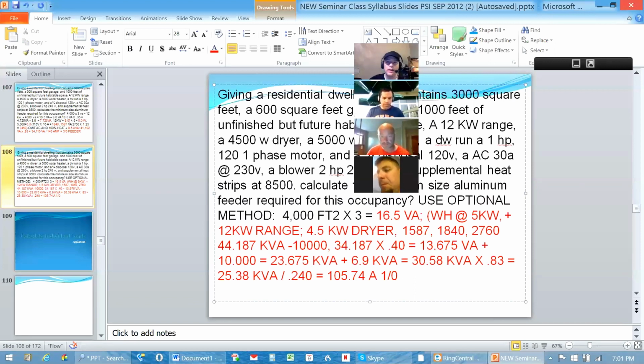Now, if they had told me that air conditioner was a heat pump, and that the supplemental strips were in addition to the heat pump values, and that they were interlocked from operating at the same time, then I would be looking at taking just 100% of the nameplate. 65% of the supplementary heat. If it's prevented from operating, you don't have to take the 65%. So it'd be a different story if there's a little bit more detail listed there. And they do sometimes give you that exact detail that falls under part 3. So you just have to look at the heat loads carefully.